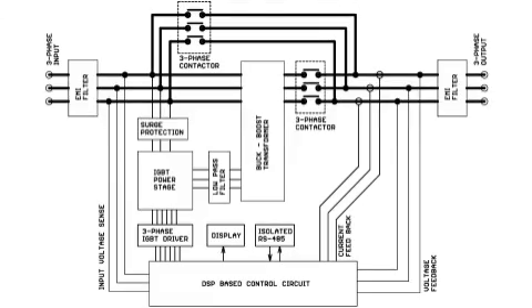This is the functional block diagram of the system. Since only the difference power is processed, much less current will flow through the IGBTs. For example, for a 100 ampere 52 volt correction in each phase, only 9.2 ampere will flow through the IGBTs. A 66 kVA system needs only 12 kVA 3-phase buck-boost transformer.